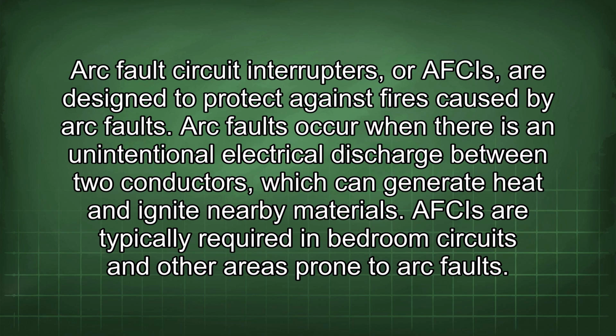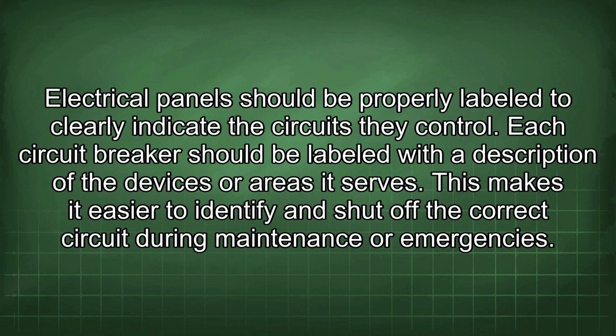AFCIs are typically required in bedroom circuits and other areas prone to arc faults. The electrical panels should be properly labeled to clearly indicate the circuits they control. Each circuit breaker should be labeled with a description of the devices or areas it serves. This makes it easier to identify and shut off the correct circuit during maintenance or emergencies.